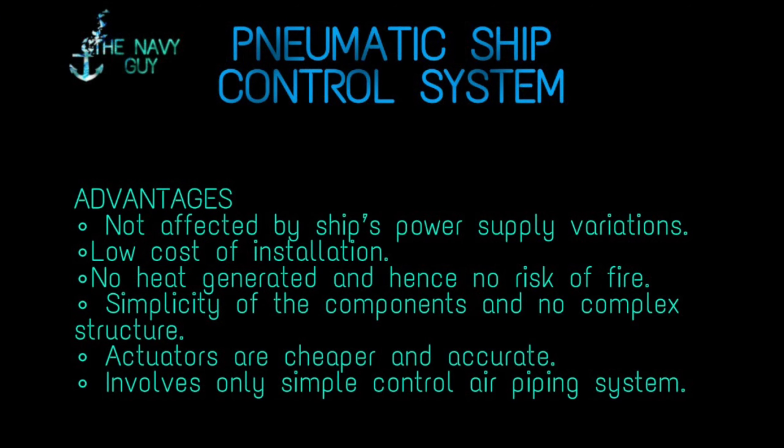Some advantages of the pneumatic ship control system are: it is not affected by the ship's power supply variations for short term; it requires a low cost of installation; no heat is generated and hence no risk of fire; the simplicity of components with no complex structure; actuators are cheaper and more accurate than electric systems; and it involves only a simple control air piping system.